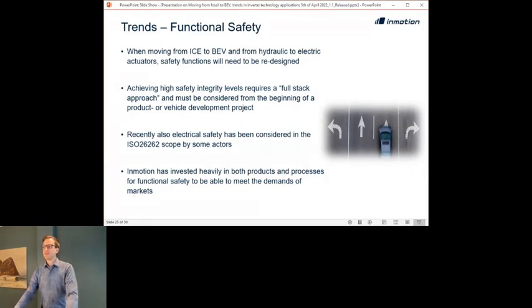One example is if you change from hydraulic to electric actuators for a machine function, where previously the safe state would be to disable hydraulic valves—that might no longer be possible. So this must be replaced with a safe state for the inverter, for example, instead.